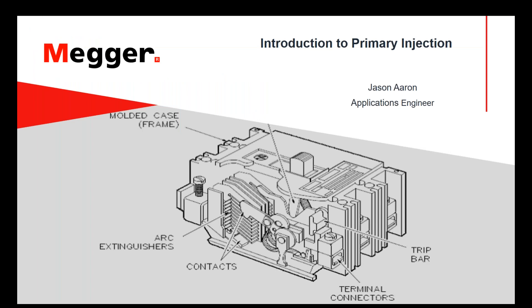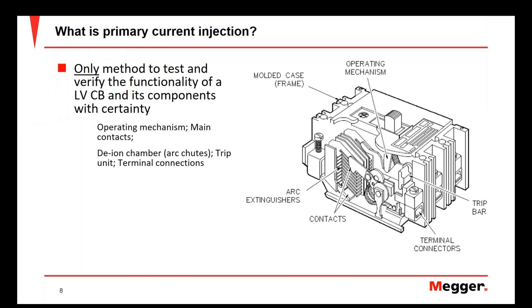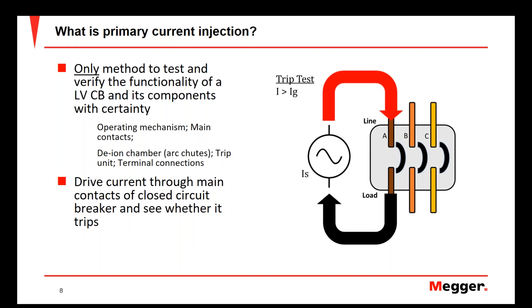Let's dive into our primary injection section. Primary current injection is the only method we can effectively use to do a functional test on circuit breakers and some other components. It is the only method that we can use to verify that all the mechanisms within a circuit breaker are going to operate as intended whenever it's in use in a real-world scenario.